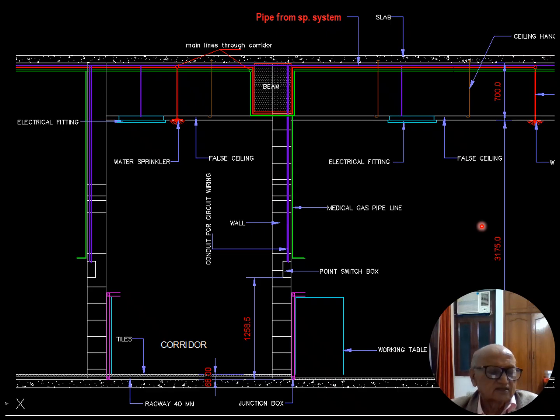Now in the right hand side diagram, you can see that the sprinkler pipe is coming and dropping down to the false ceiling, and after taking the profile of beam, it is going to the other room. Now here it is dropping to this one. This portion is known as ceiling hank. Ceiling hank is the area between real slab and false ceiling, and this is somewhat more hot than the room itself if the system is air conditioned.